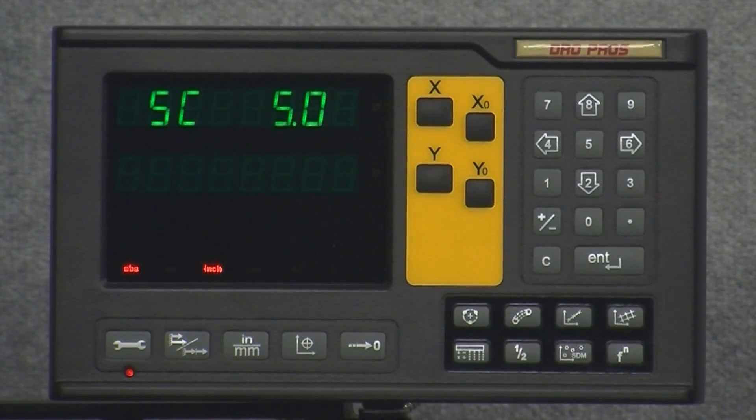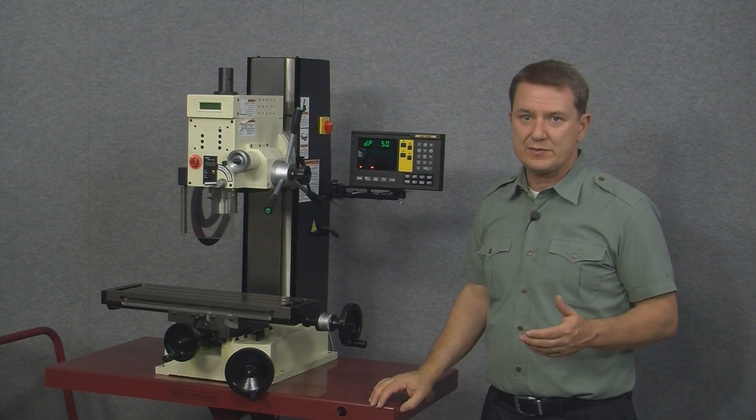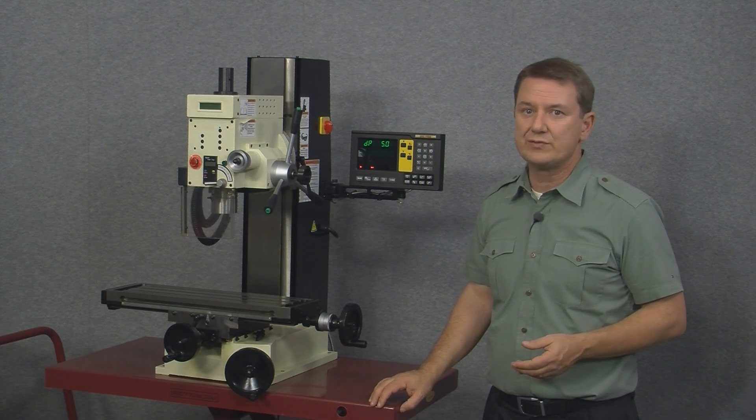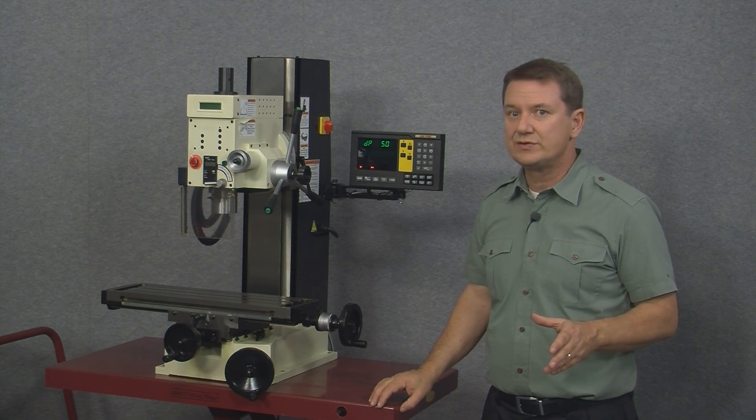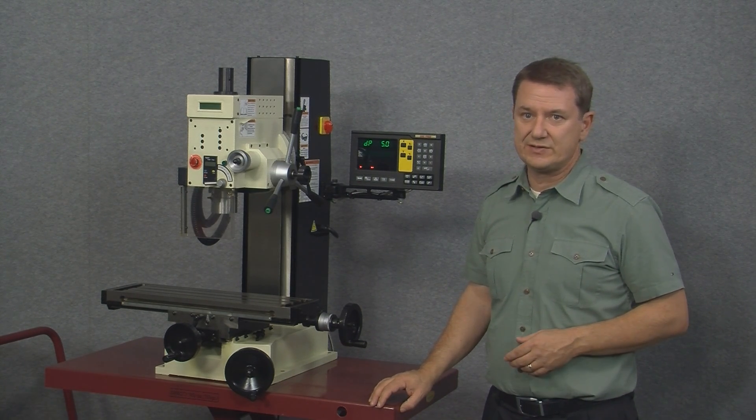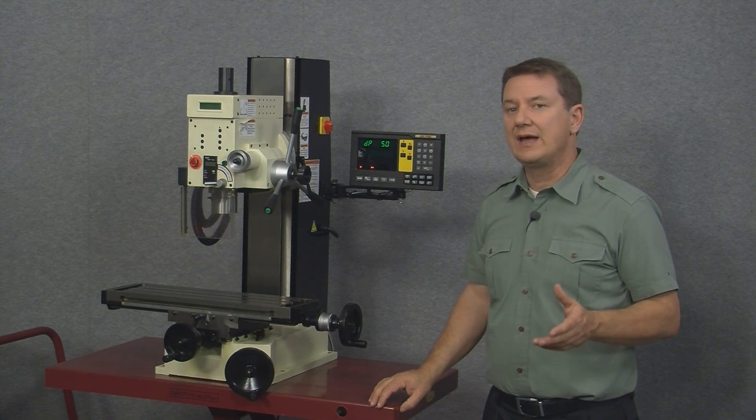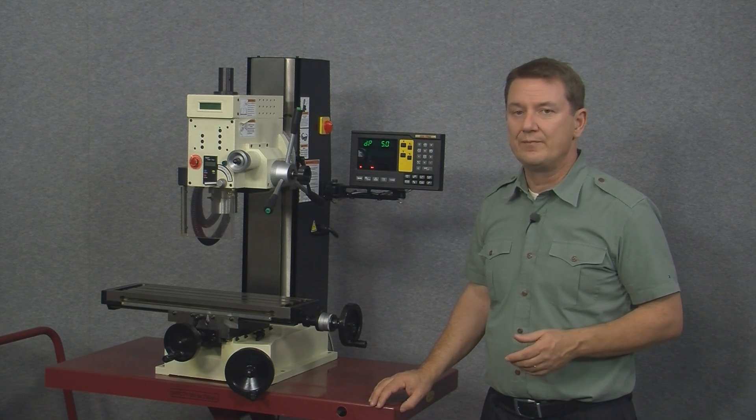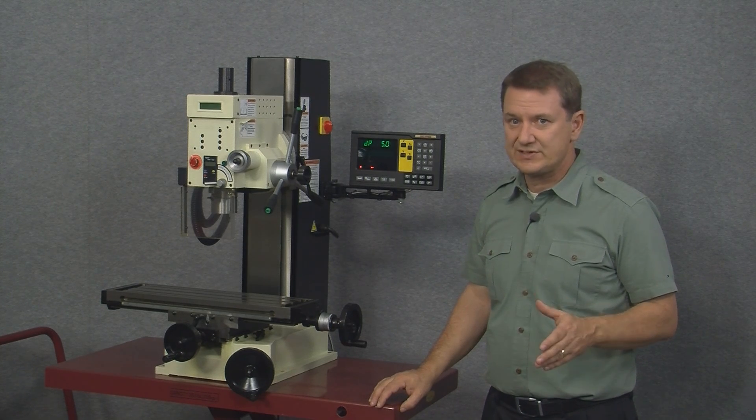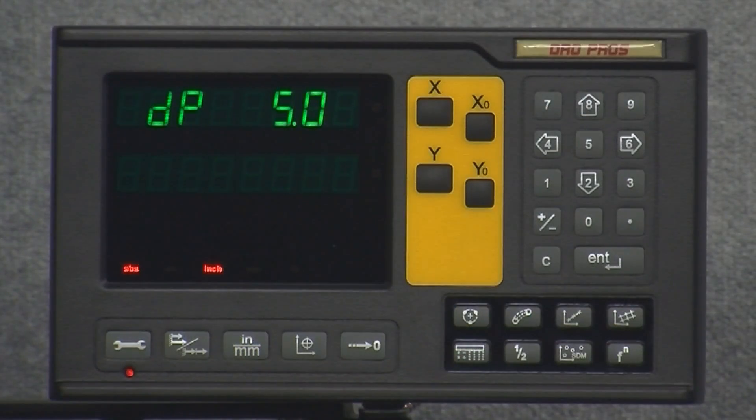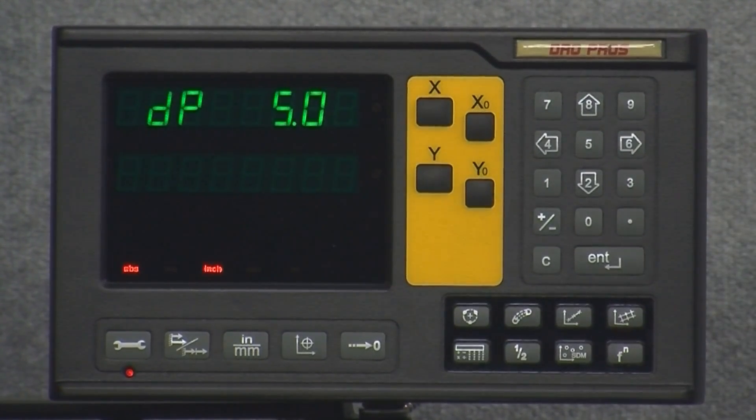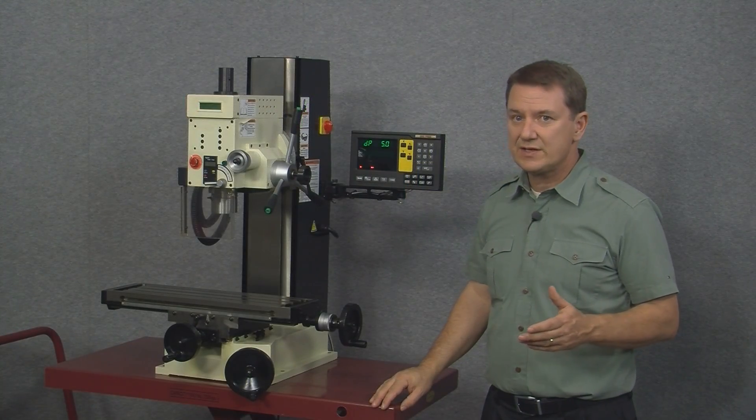So let's arrow down. And next, we see DP 5.0. Now, this setting represents the display resolution. And this setting is user selectable and can be changed to whatever suits you best, as long as it's equal to or greater than the resolution of the scales you have. Let's go ahead and take a look. Again, the default is 5.0 or 5 microns, just like before. And this option also has more than just two settings. And if we arrow left or right, we can again scroll through all of the different choices.